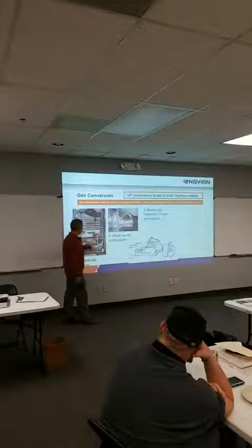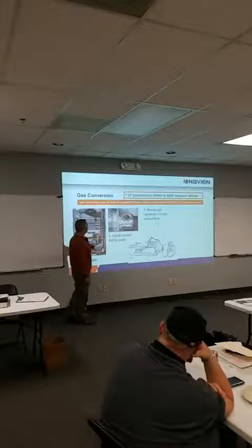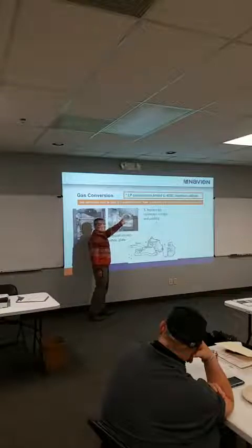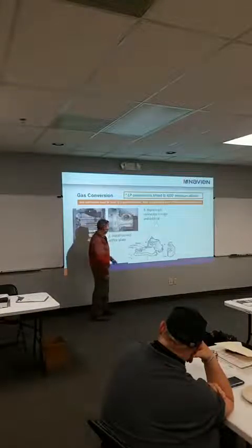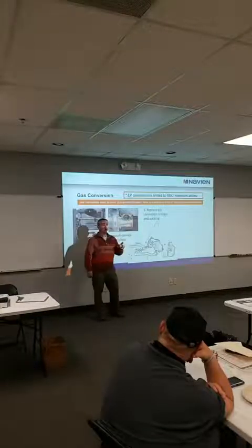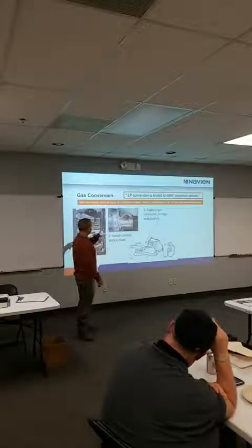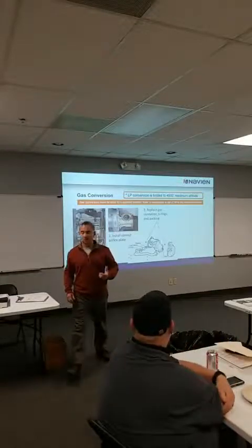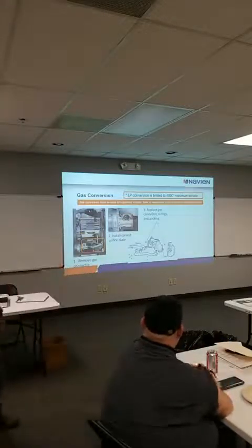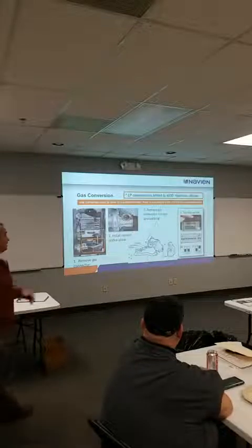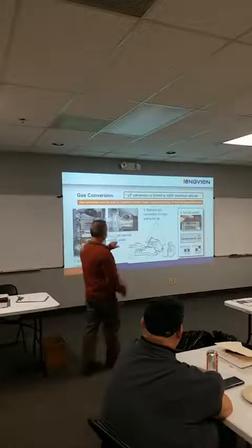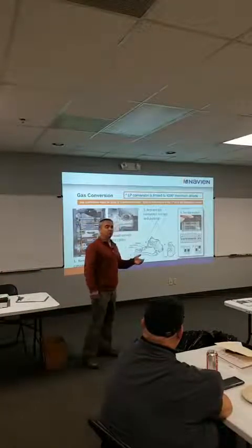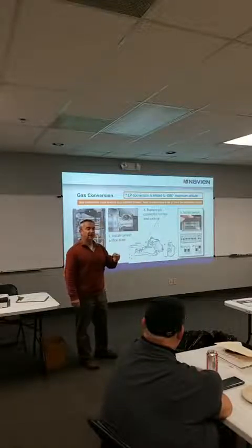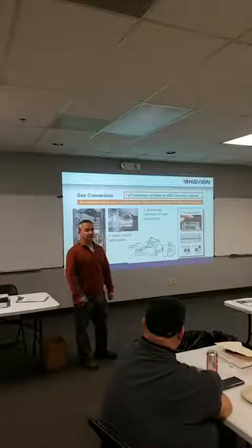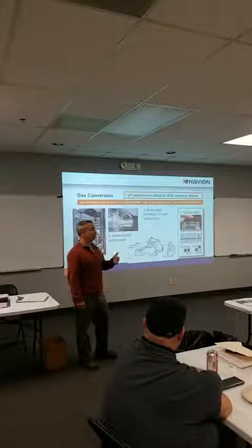We basically pop the bar off, there's 4 screws, 2 screws, and the orifice plate comes out. It will have the model number and say NG on it. The new orifice plate will have the model number and say LP. You swap those 2 out, put the bar back on, and then it's a simple dip switch. On the NHB, that dip switch is the last one above the keypad. On all the new units, it's going to be on the side of the keypad or on the board itself, that one dip switch. And that's your LP conversion, you can go back and forth as many times as you want.